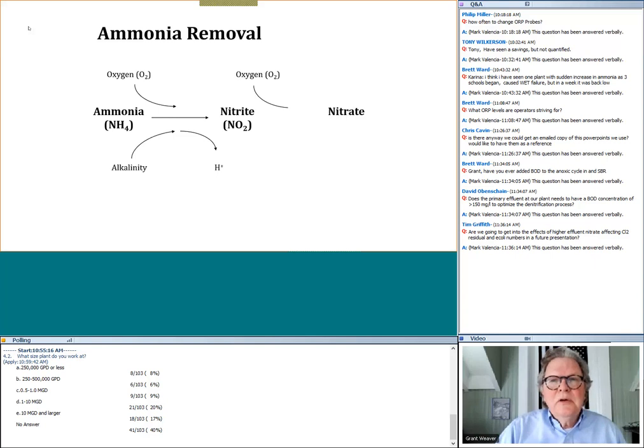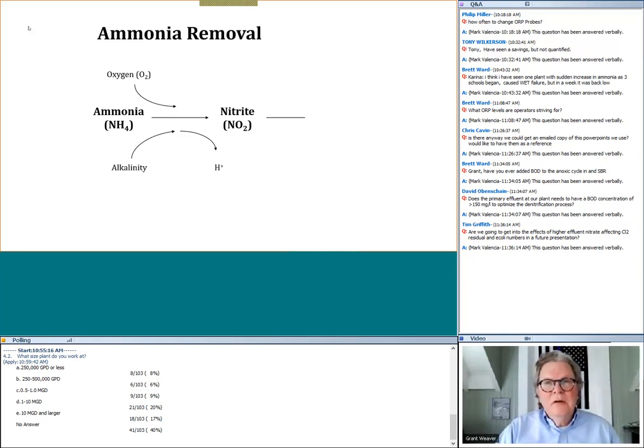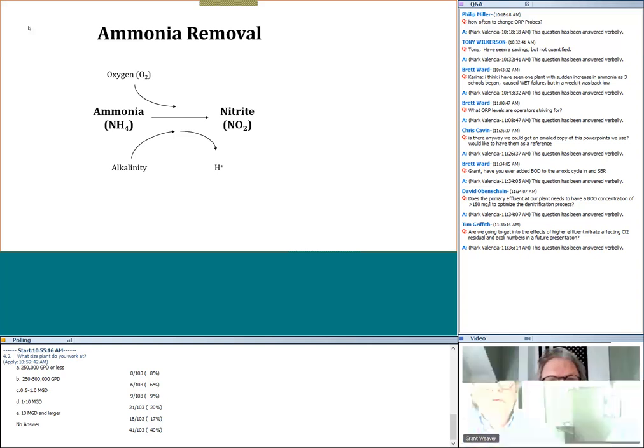Now, once you're up and running, you have bacteria that do this growing and the bacteria that produce nitrites. So once you're there, the pH is consistent, you're going to have almost no nitrites, 0.1, 0.2, 0.3, definitely less than 0.5 day in and day out, milligrams per liter. But the problem with nitrites, as the questioner knows, was stimulating a discussion, is if you chlorinate this organic form here, nitrites, it'll grab the chlorine before it'll bind it up, so it's not available as a disinfectant. So I think it's something like 5 times as many milligrams per liter of chlorine as there is nitrite.